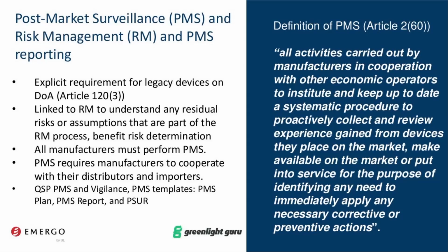Of course, post-market surveillance is linked to risk management and understanding of residual risks, and also to the benefit-risk determination. We all know that all manufacturers must perform post-market surveillance, and as we elaborated before, all manufacturers, irrespective of whether they are compliant to the MDR on the date of application or they are legacy devices, must perform post-market surveillance compliant to the MDR. Because of all this, we would recommend that manufacturers start to develop as a priority their procedures on post-market surveillance and vigilance, as well as the necessary post-market surveillance templates: the post-market surveillance plan, the post-market surveillance report, and the periodic safety update report.